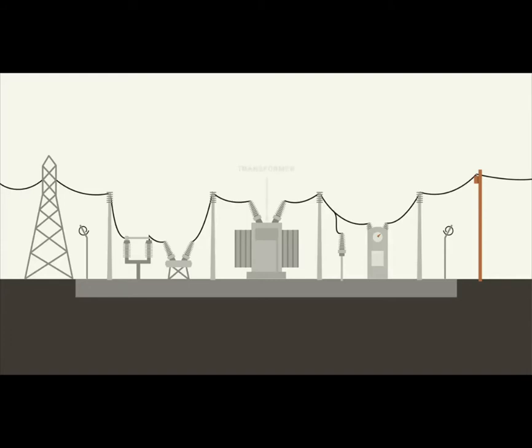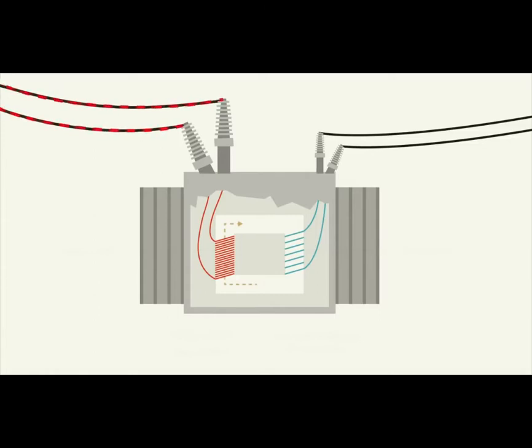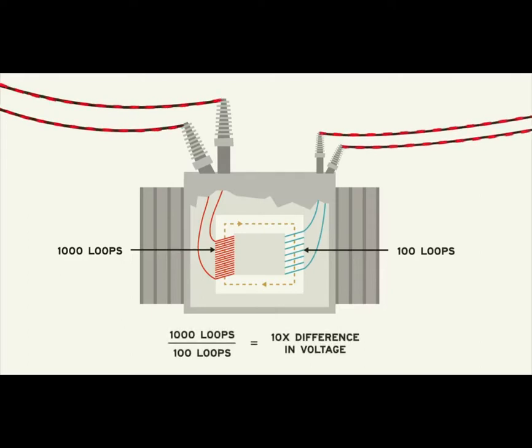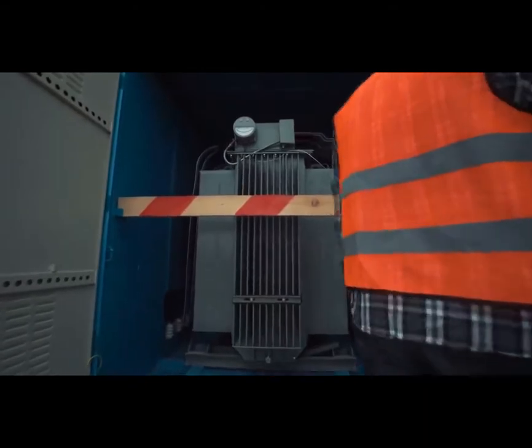Voltage is reduced using transformers located within a substation. A transformer is an extremely simple device that relies on the alternating current of the grid to function. It consists of two adjacent coils of wire — as the voltage in one coil changes, it creates a magnetic field, which couples with the other coil, inducing a voltage. The incredible part has to do with the number of loops in each coil: the induced voltage is a function of the ratio of the loops. For example, if the transmission side has 1,000 loops while the distribution side has 100, the voltage on the distribution side will be 10 times less. This simple but remarkable fact makes it possible to step up or down voltage as necessary to balance safety and efficiency along each part of the power grid.